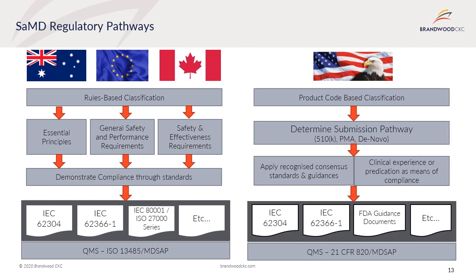To meet the mandatory requirements, typically standards are applied to demonstrate compliance. The key standards cover software development, usability, information security, and so on. All required documentation is then compiled into a technical file for each device or family of devices. A technical file is then assessed by the relevant regulatory body for registration of the device, except for Class 1 devices which involve a self-declaration process. Finally, local representatives are appointed within each jurisdiction with varied responsibilities.